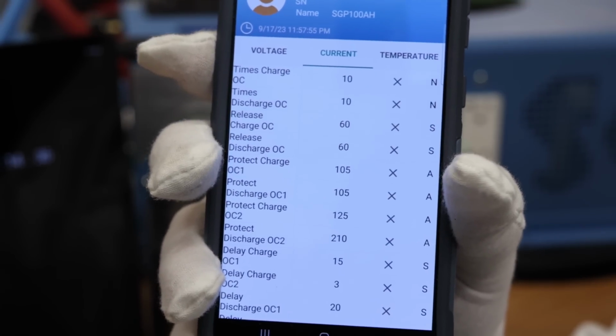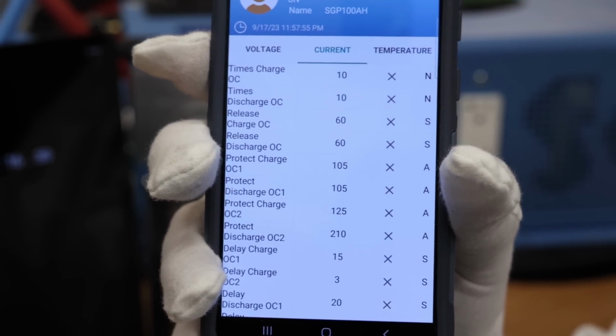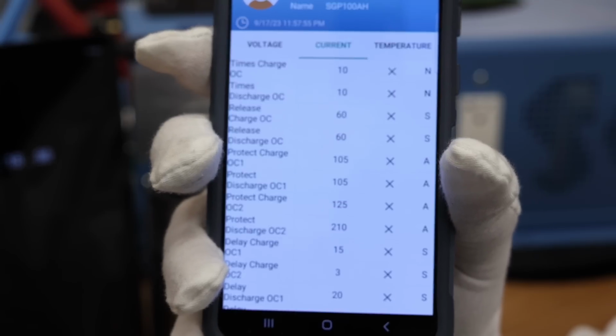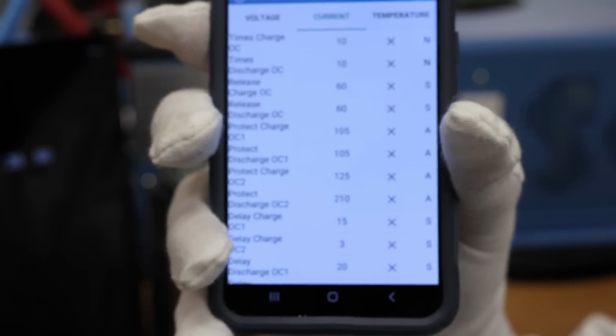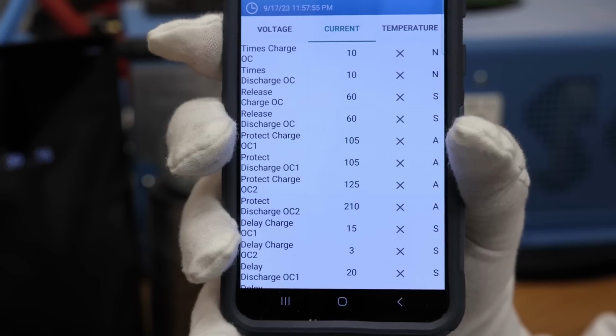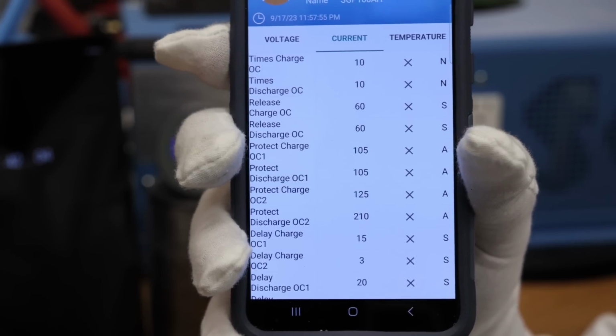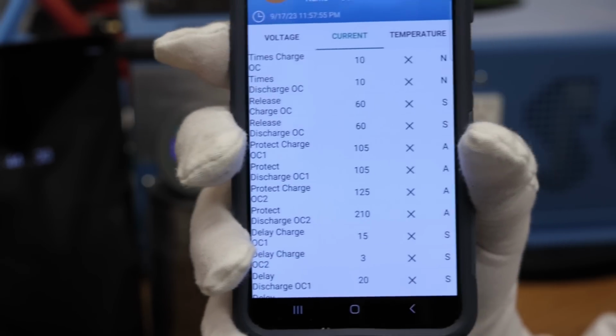It tells you the limits. It says right there, protect charge OC 105, that's 105 amps, and the delay is 15, probably 15 seconds, with another delay of 3 seconds. So you can see the settings right here showing the limitations of the battery.